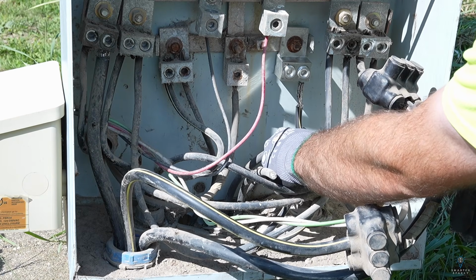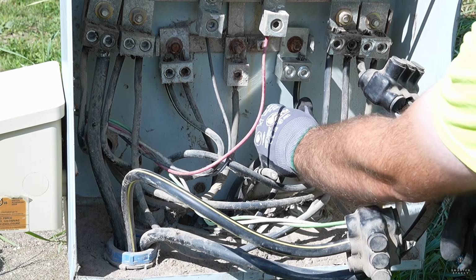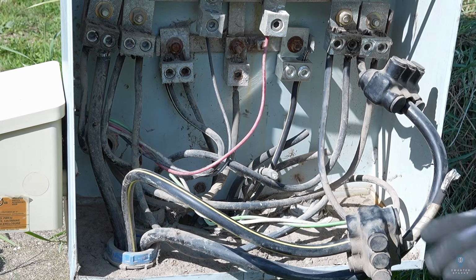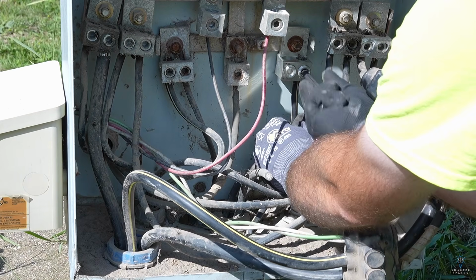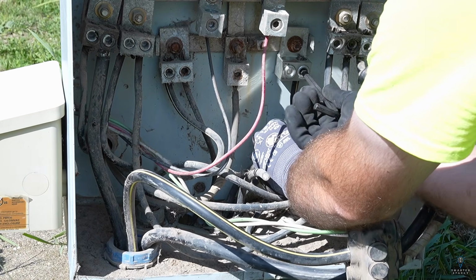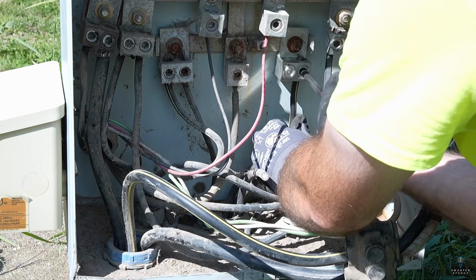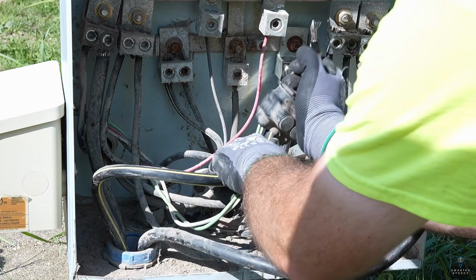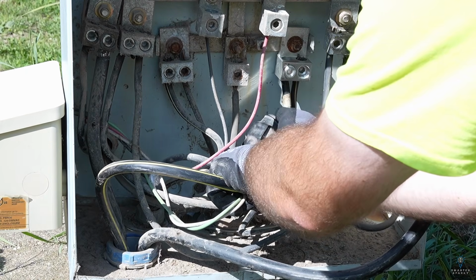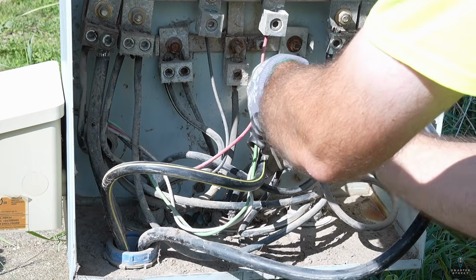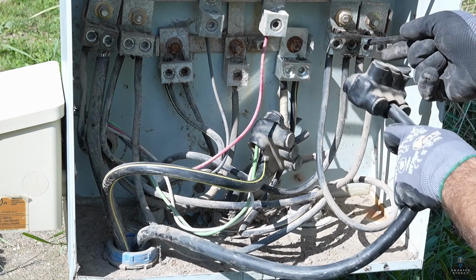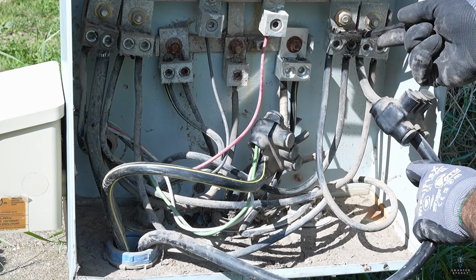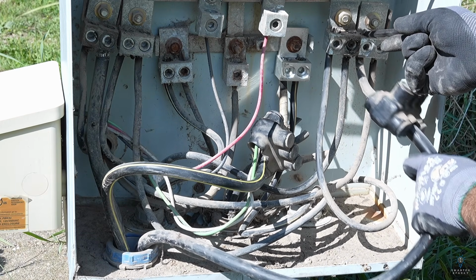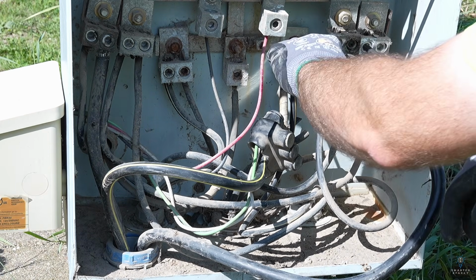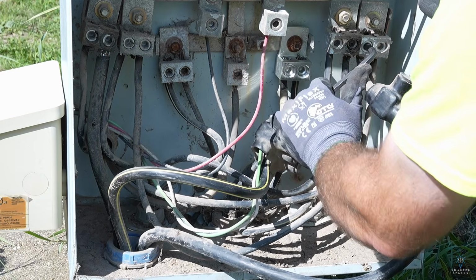All right, we'll put the shop neutral back on. Shop neutral we'll put right there. And right now I'm just gonna snug this down with the Allen wrench, and I'll tighten it down further in just a minute. And then the neutral for the house, swing up there. Like I said, this hot looks a little loose here. It's caught really good on like 2 of the conductors, but the rest of them are loose. So we're gonna fix that while we're here as well.